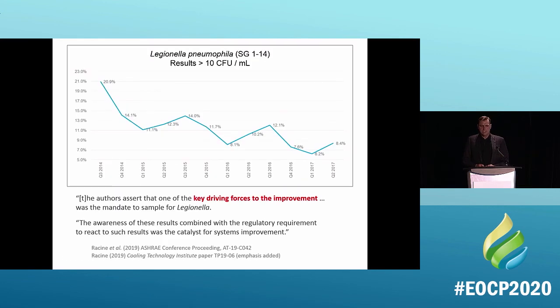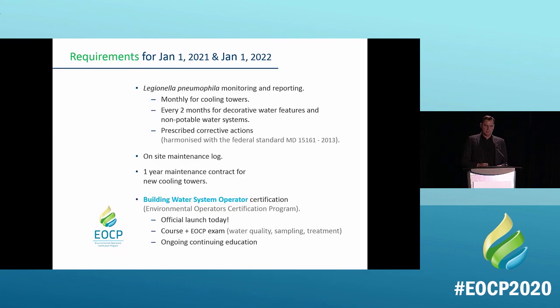Legionella pneumophila gets the most attention. When Quebec had their big outbreak, the province said everybody needs to register their cooling tower. So everybody registered, and then they started doing testing, because you can have the best maintenance program, but if you don't test, you don't know if it's working. When Quebec started their program, 21% of cooling towers tested positive for Legionella - 1 in 5, which nobody expected. But just through testing and changing their biocides or maintenance methods, they drove that number down, and by Q2 of 2017 it was hovering around 8%. That's a drastic change, and it came just from testing to figure out if their maintenance was working.